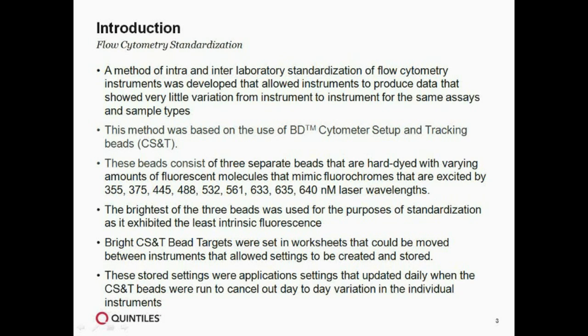That method is based on beads developed by BD called Cytometer Setup and Tracking beads — CS&T beads. These beads consist of three different staining intensities. They don't contain the exact fluorochromes you would run, but they have fluorescent molecules that mimic fluorochromes excited by all the various laser wavelengths commonly used in flow cytometers. We used the brightest of these beads for standardization because it exhibits the least intrinsic fluorescence from the bead itself — most beads are polystyrene and have their own autofluorescence — giving the best possible CV and the least bead self-fluorescence contribution.